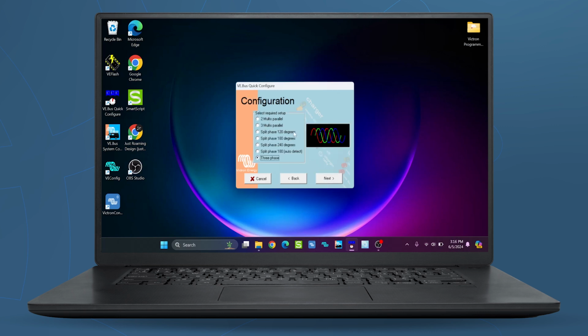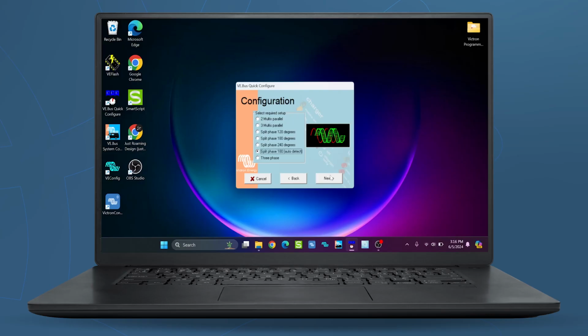However, during the configuration, now we're going to select Split Phase 180 with Auto Detect. This auto detect portion means that there's some flexibility in what it's looking for. So if you're plugged into a 3-phase 208 system, say at an RV park at the pedestal, you'll be able to pull and operate off of that regardless of whether there's a slight variation in that voltage.